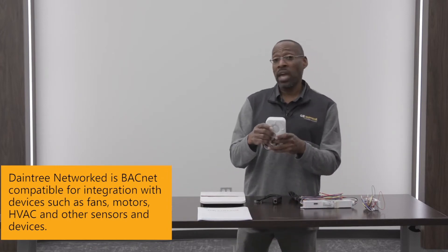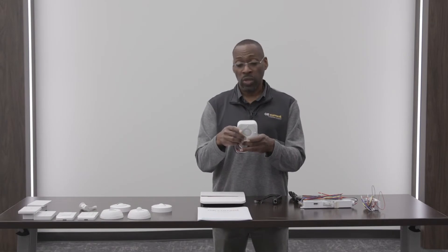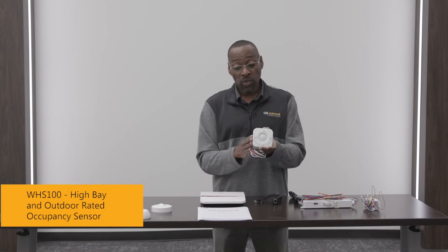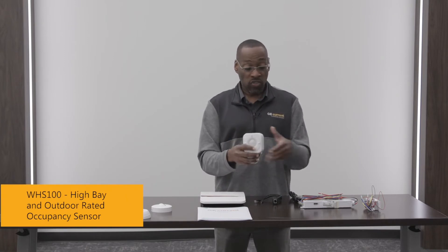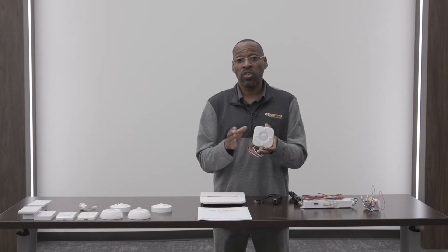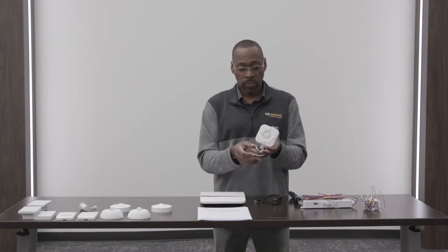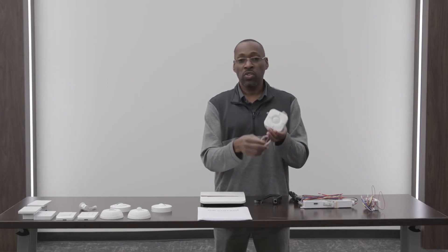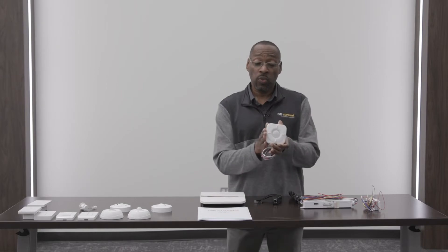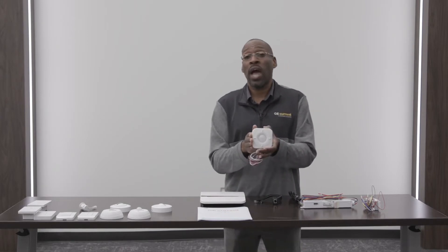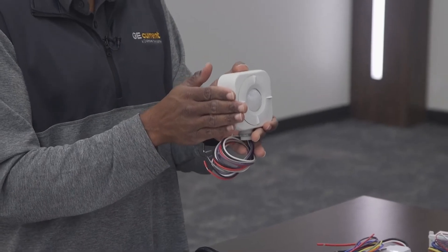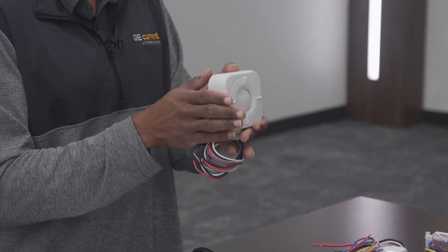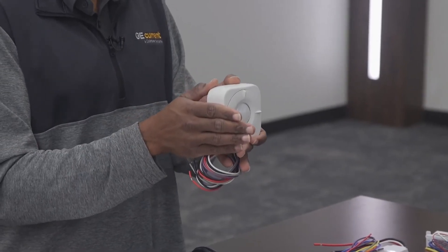For our high bays and some of our warehouse utilization lighting systems, this is the WHS100. The WHS100 can control devices similarly to the WA100 — cutting them on and off and also dimming. You power up the device, connect your purple and gray wires, which are your dimming loop to dim the device. A great feature of this device is that it can sense whether it's an on/off light or whether it just dims the lights. It has a 0 to 10 volt dimming sink in it, so that's how we control dimming from 0 to 10 volts.